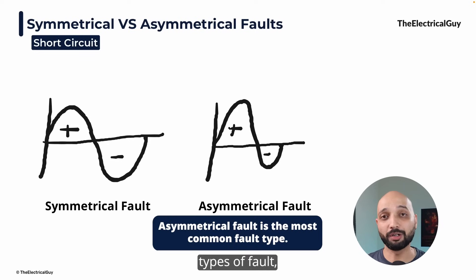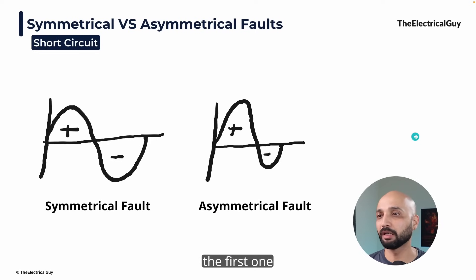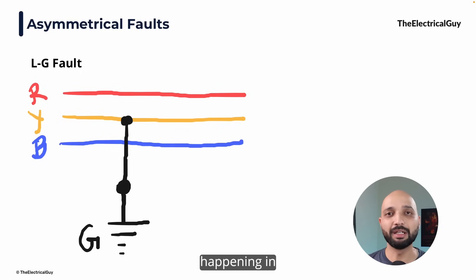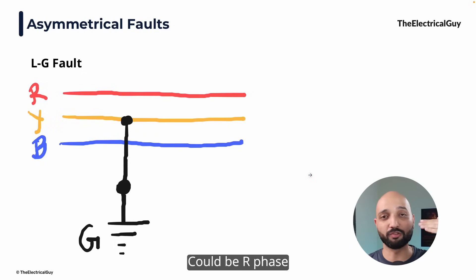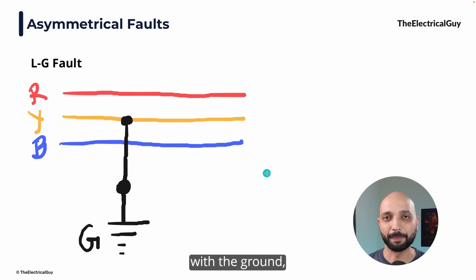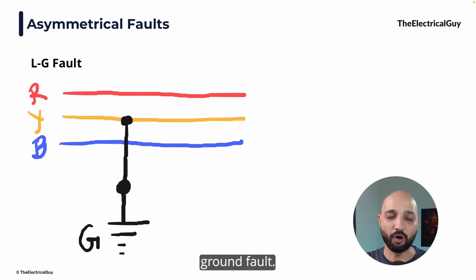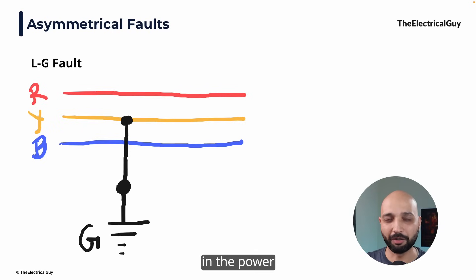Looking at the different types of asymmetrical fault, the first and most common type is the line to ground fault. What is happening in this fault is one of the phases — it could be R phase, Y phase or B phase — is getting connected with the ground, creating a short circuit. That is what we call an LG fault or line to ground fault. It is the most common type of fault in the power system and occurs very, very frequently.